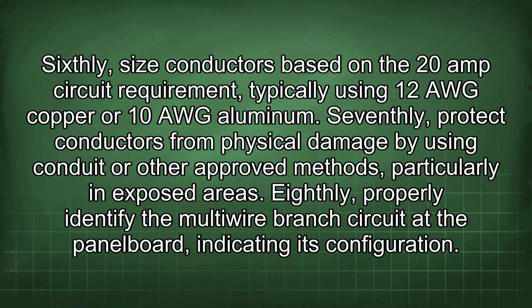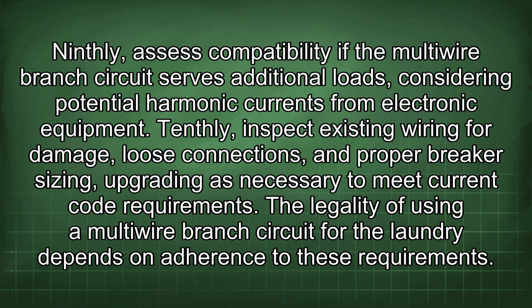Sixthly, size conductors based on the 20 amp circuit requirement, typically using 12 AWG copper or 10 AWG aluminum. Seventhly, protect conductors from physical damage by using conduit or other approved methods, particularly in exposed areas. Eighthly, properly identify the multiwire branch circuit at the panel board, indicating its configuration. Ninthly, assess compatibility if the multiwire branch circuit serves additional loads, considering potential harmonic currents from electronic equipment. Tenthly, inspect existing wiring for damage, loose connections, and proper breaker sizing, upgrading as necessary to meet current code requirements.